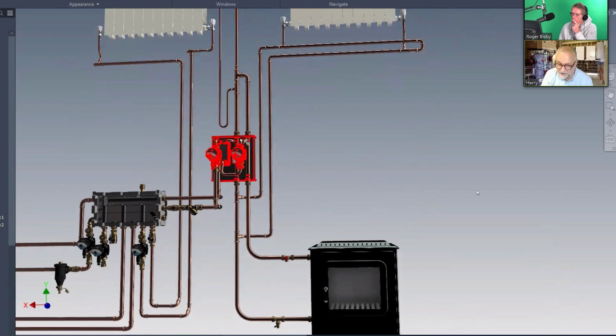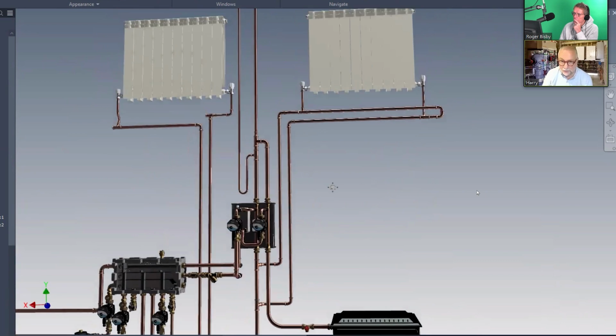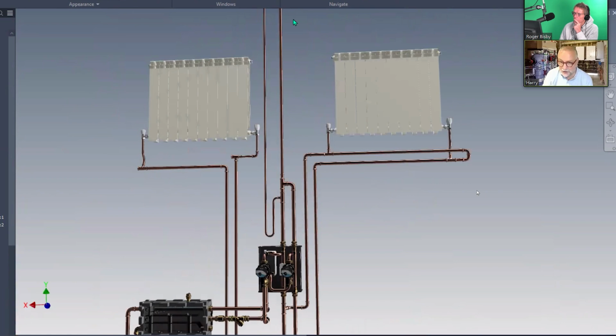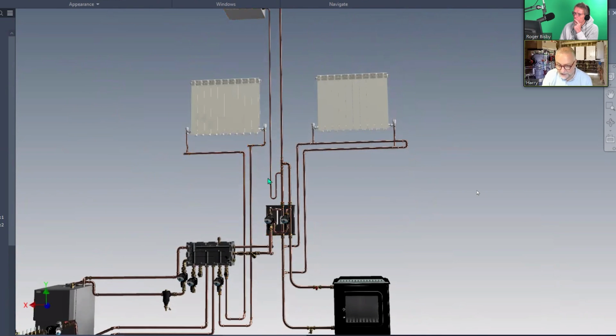So when this is falling down, it comes to this T first, and it does what nature tells it to do. It rises, and then it goes round this loop. If it was going through a radiator valve, it has resistance. But by doing this, it has a perfect circuit. When it gets to here, it rises. When it gets to here, it falls. And now it falls into this loop, and it falls back down, and so it's 100% safe. Your expansion is exactly where it should be. Your cold feed is completely protected with a heat leak. It's by the book correct. And so the solid fuel side could not be simpler and could not be easier.